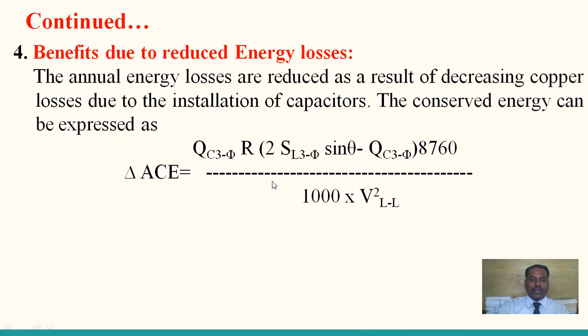Based upon this magnitude, you may predict how much losses are reduced over an annum. Here, annum in the sense per year. A year has 24 into 365 days, so 8760 is the total number of hours per year. Delta ACE is equal to QC 3 phase into R into 2 into SL 3 phase sin theta minus QC 3 phase into 8760 divided by 1000 into V line to line whole square.